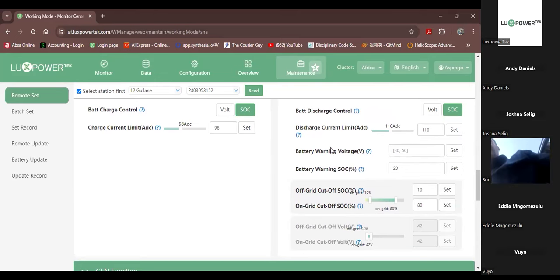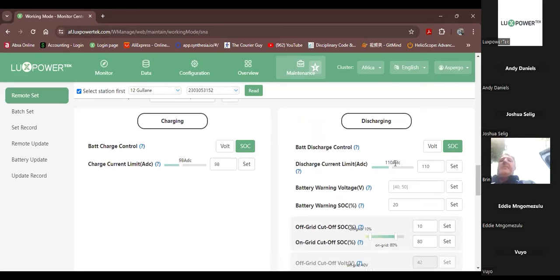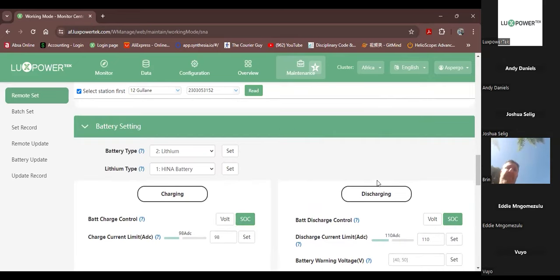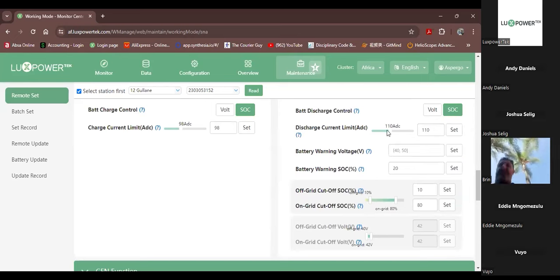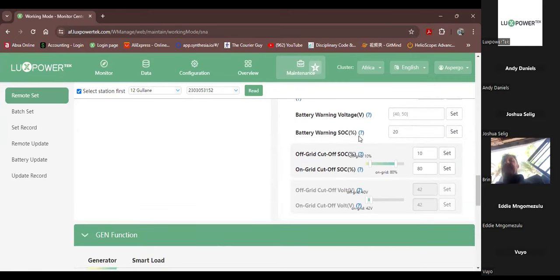On this side here, we have the discharge control. And here you can see that this particular machine is preset to 110 amps DC because the SNA can handle that kind of discharge because of the fan cooling. And also because this machine has got a high-spec battery, we've allowed that. But if you want to extend the life of your battery according to the manufacturer, then you can set your current discharge here to a lower value.